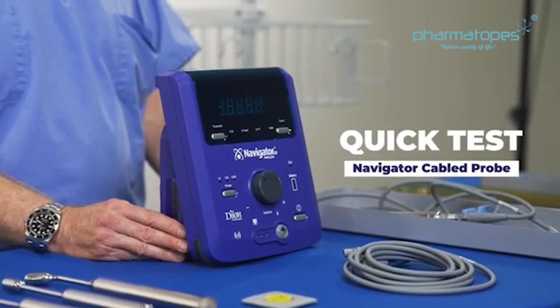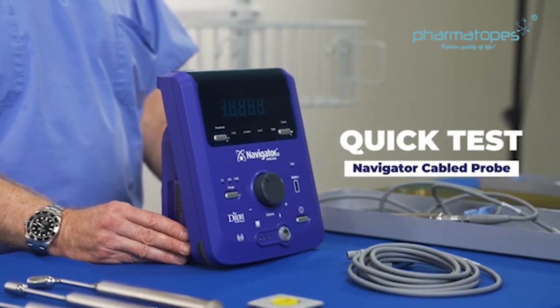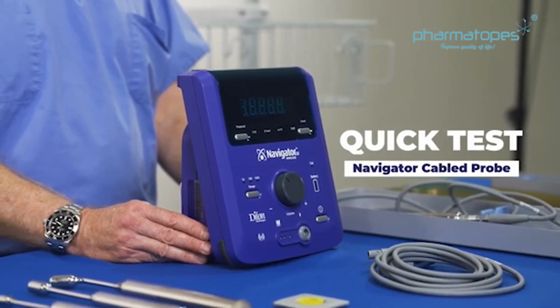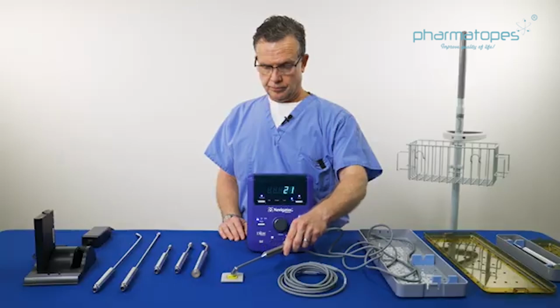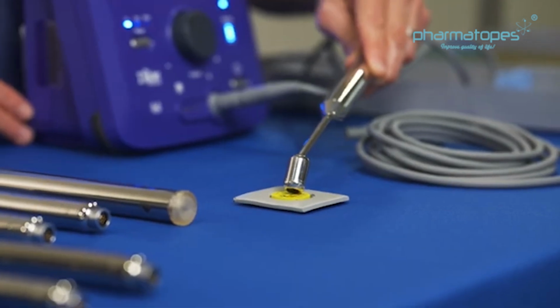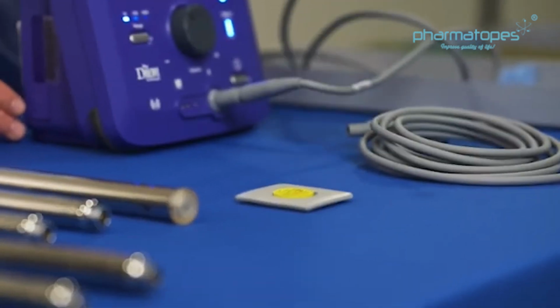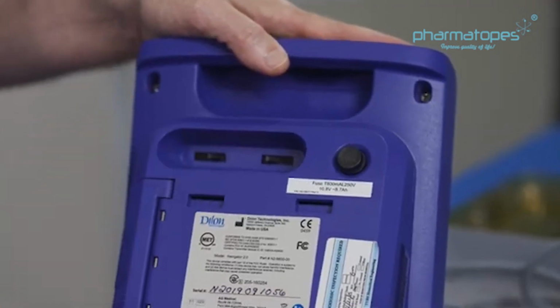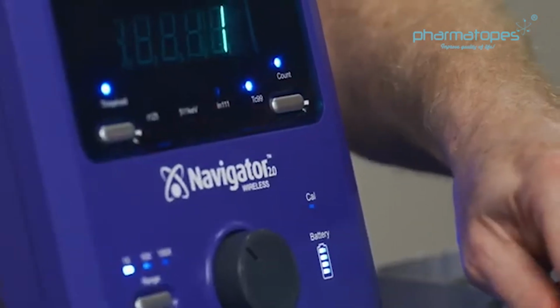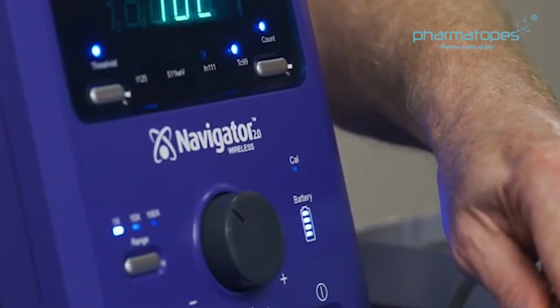Every 6 months, you can perform this quick test by following these simple steps. This test will help to make sure the probe is in optimal working condition. You can use a test check source to hear the sound and read the counts. While holding the probe steady on a check source, perform the following measurements. Set the switch to the positive setting. The calibration light will blink, indicating that you are in testing mode.